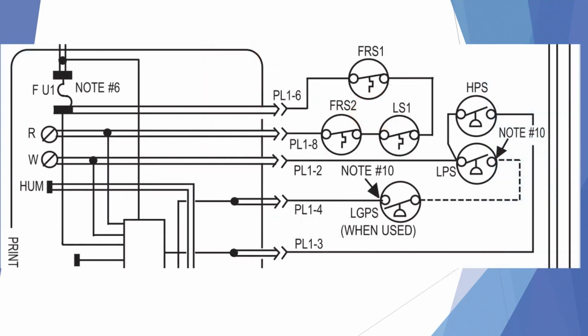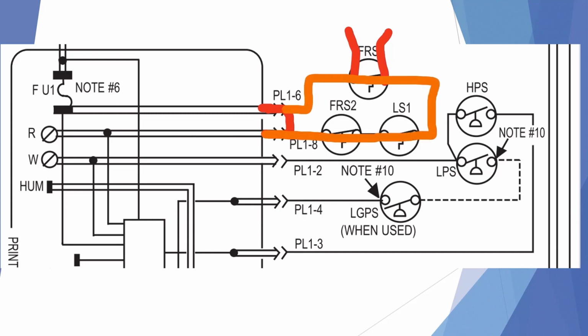Here's another example where we're checking a flame rollout switch to make sure that it's closed so that the furnace will operate, and we find the switch is closed, but the furnace will still not operate. So here again we would direct the technician to jumper the flame circuit at the board to eliminate the wiring and the plugs. This would eliminate anything out in that circuit, and if it works by jumpering at the board, then we know that a plug or a wire is defective in that circuit.